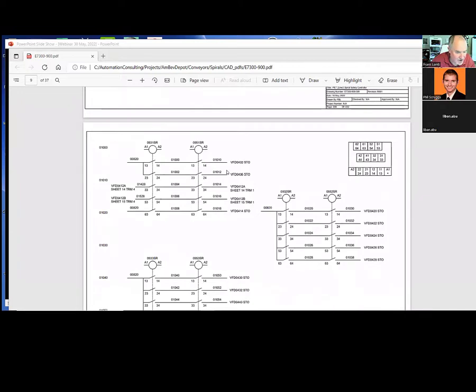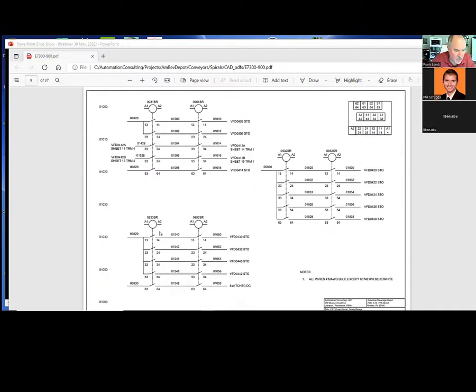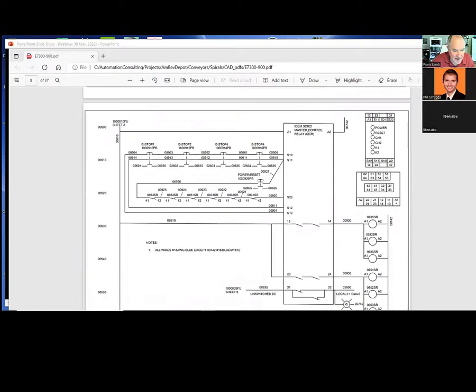These drawings go out to the safe torque off on the drives, and in this case, this is the case turner. None of this is particularly dangerous, it's just conveyors, not a super hazardous setup. But I told Juan Pablo this is a good opportunity to wire things up the way you would for hazardous equipment later, like robots, where you'd have to remove power on 2 channels. You want to do things the right way and use a safety relay like this.